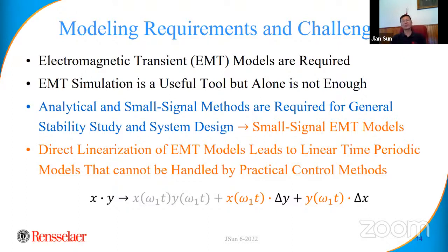But we cannot use those models for the high frequency dynamics. They're happening within every fundamental cycle, so your fundamental frequency model is not going to be able to capture that. We need EMT models. So the starting point for stability analysis in the EMT frequency range has to be EMT models - naturally, you have to start with EMT models.